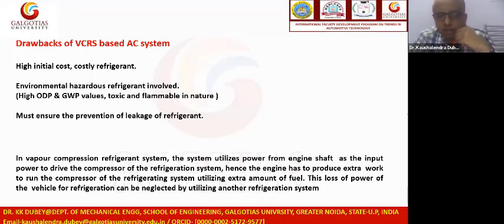Because this type of refrigerant has a small compressor size requirement, because in vehicle system design and development we cannot go for a bulky system, we cannot go for a system which occupies more space. So this is the main restriction in adopting the VCR system with high ODP and GWP type refrigerants.